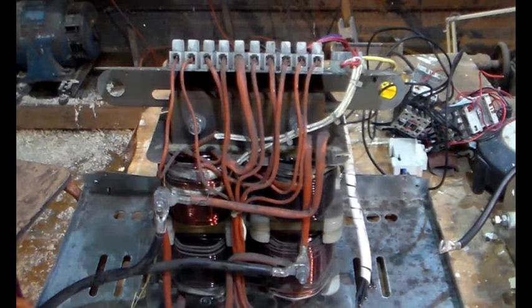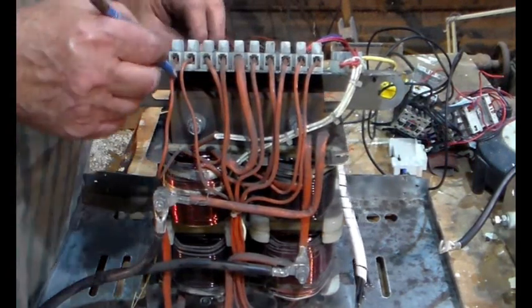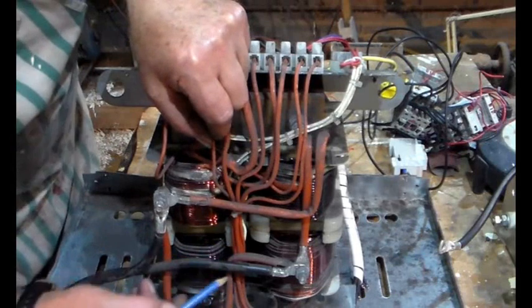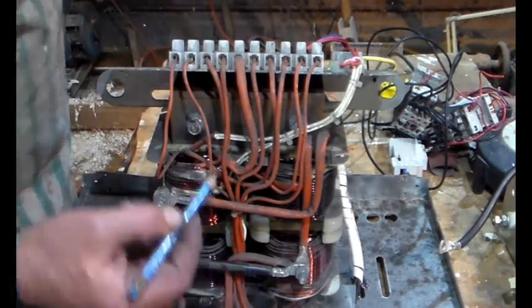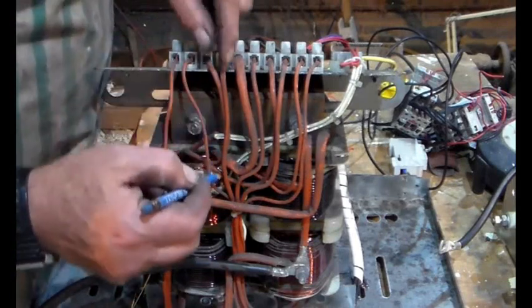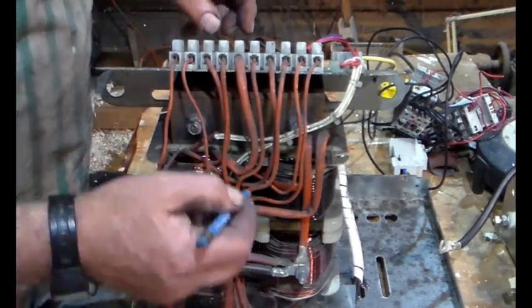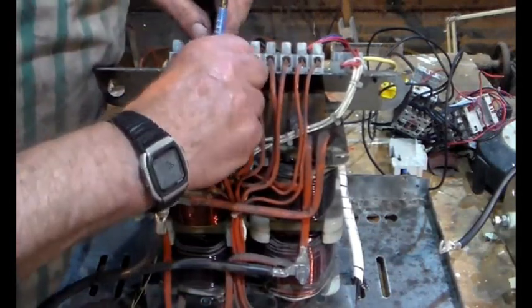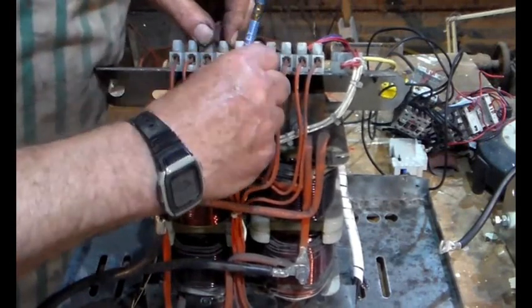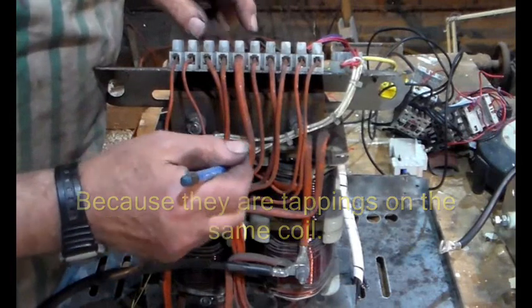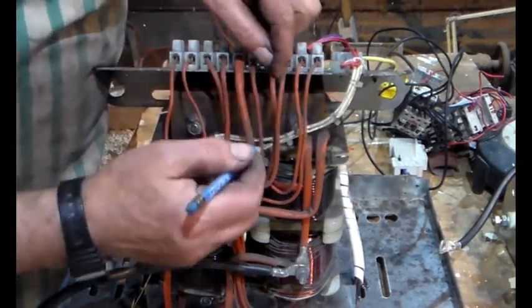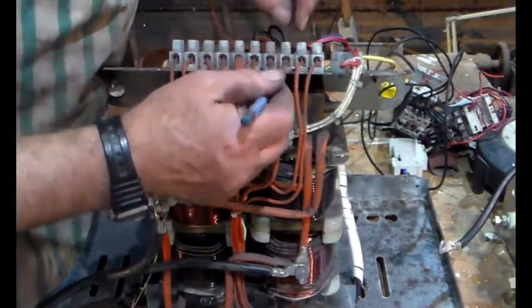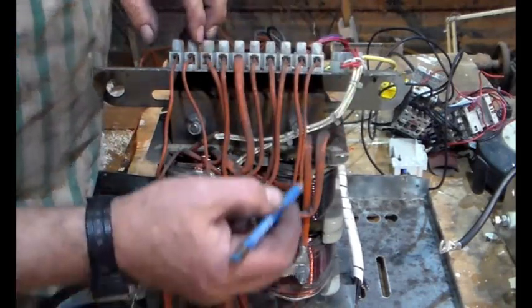Right, here's the other side. That's a 240 volt tail to that one there, and then the 240 volt tail goes down there. The 230 volts one goes there, 220 the same. The zero goes along here, the other zero goes down here.